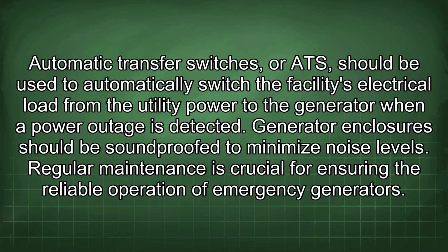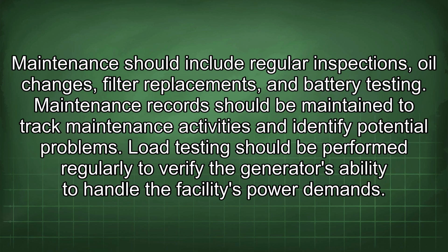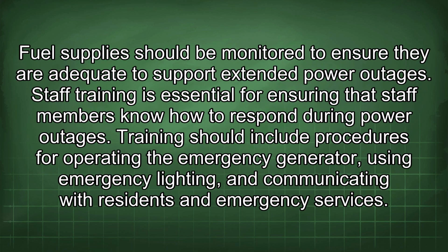Regular maintenance is crucial for ensuring the reliable operation of emergency generators. Maintenance should include regular inspections, oil changes, filter replacements, and battery testing. Maintenance records should be maintained to track maintenance activities and identify potential problems. Load testing should be performed regularly to verify the generator's ability to handle the facility's power demands. Fuel supplies should be monitored to ensure they are adequate to support extended power outages.